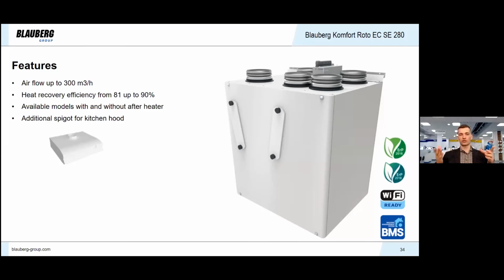Gases from your kitchen would be transported to the unit. The fan impeller of the unit would evacuate those gases to outdoors. But at the same time, these gases will not pass through the heat exchanger. We only utilize the power of the fan to extract air from your kitchen. As for characteristics, this particular unit has an airflow of 300 cubic meters per hour and a relatively high rotary unit heat recovery efficiency from 81 to 90%. Also, it is available with or without a comfort heater. But truly speaking, the most popular one is with a comfort heater.